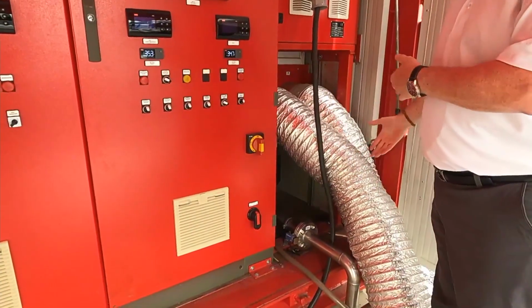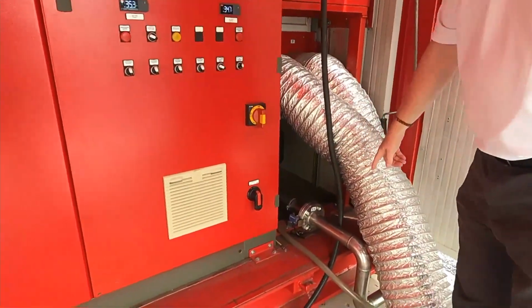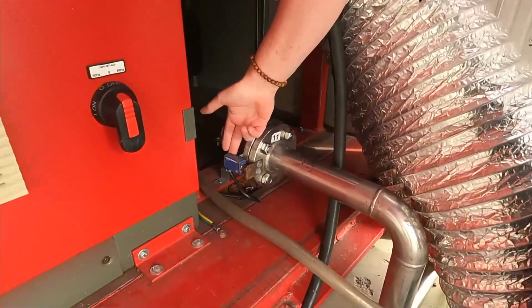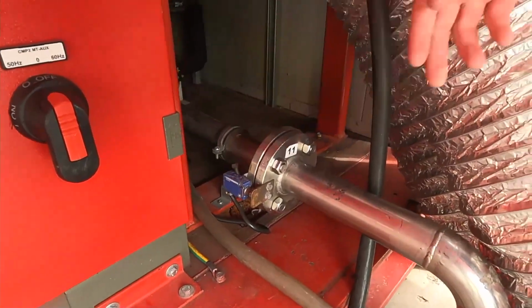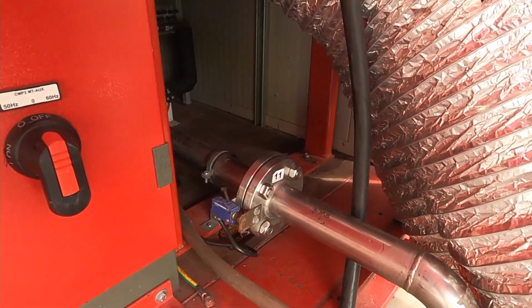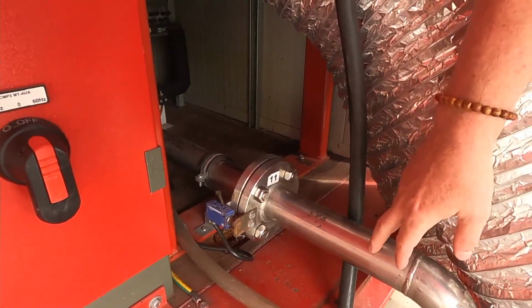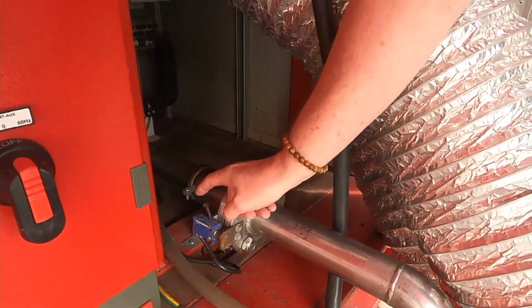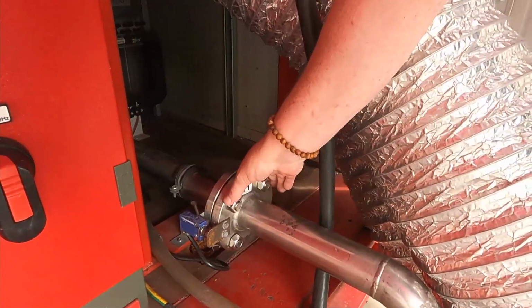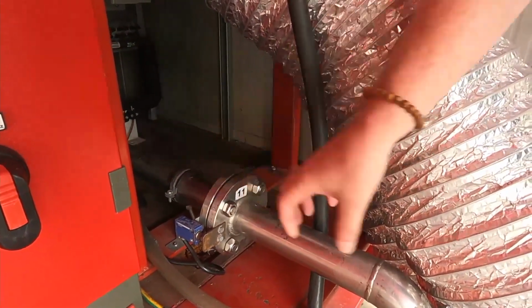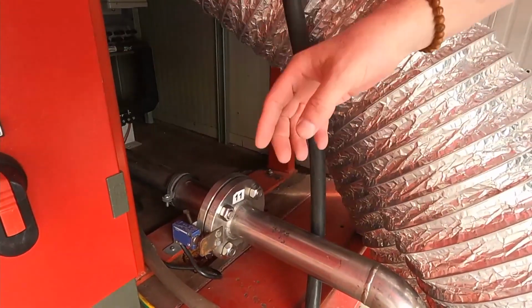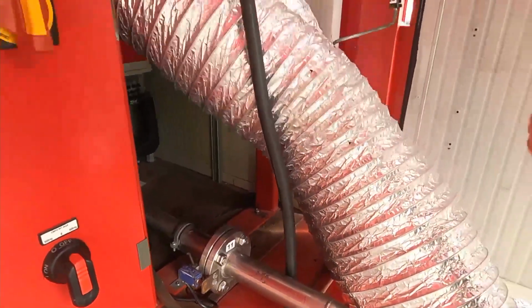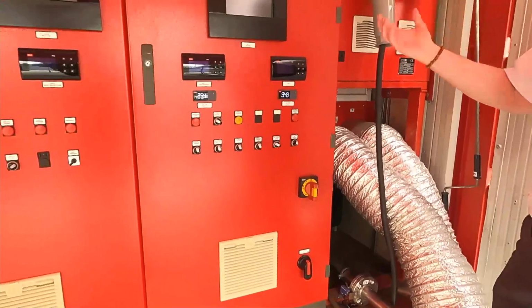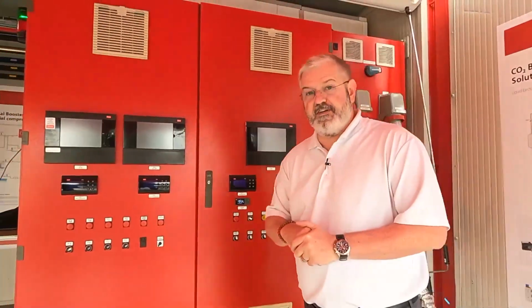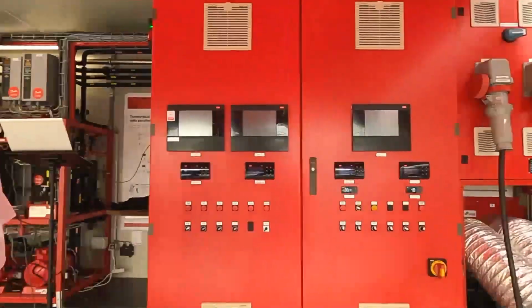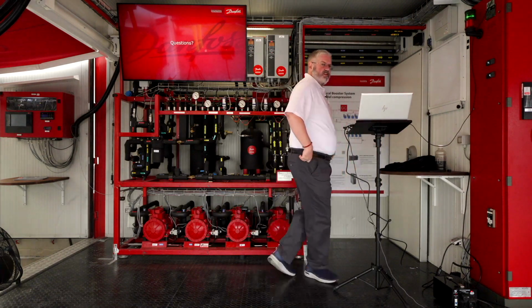For us, it's just outside the unit in this stainless steel piping, and we have a digital contact here to let us know that that's been installed or not. If we don't have this installed, the unit won't run. So the red and green light you saw is turned on and off by this. When it's connected and safe, the light is green. If it's disconnected and unsafe, the light will be red and the system won't run. So it's kind of a dummy light to tell me, hey, dummy, you need to connect the relief valve piping. Thank you. I hope that answered your question.